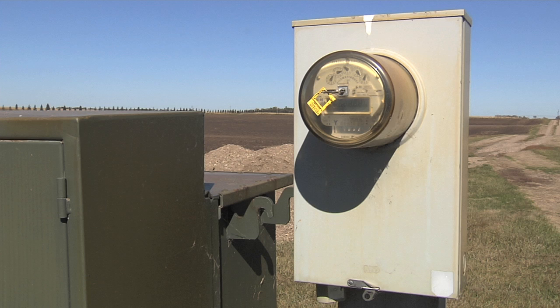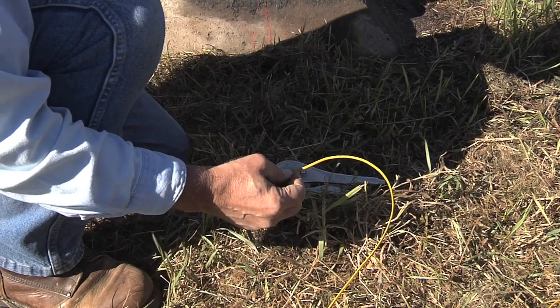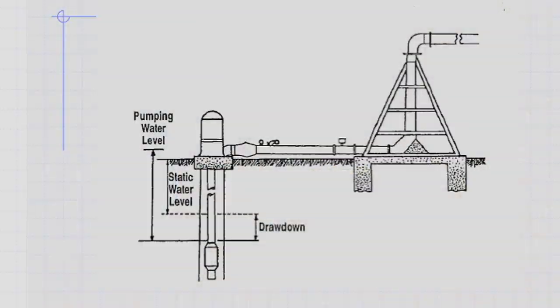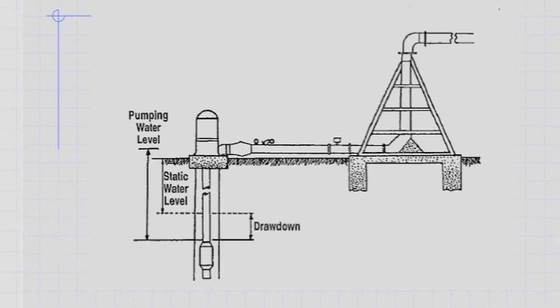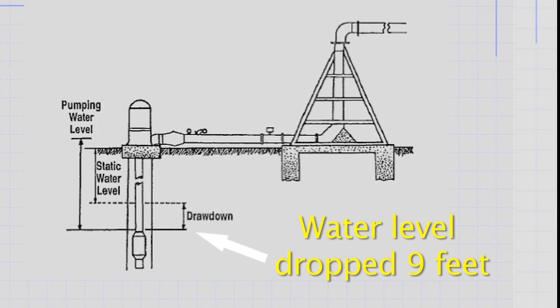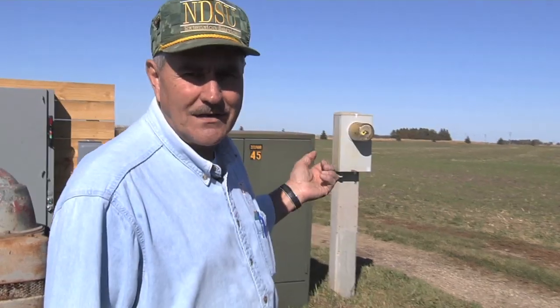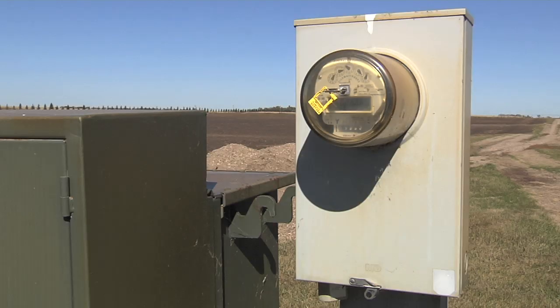And then when we get our electrical reading, we can compare the two and determine what the efficiency of this pumping plant is. It says 186, and we started at 162, so that means we've got 24 feet of pumping water level. So at 600 gallons a minute, this has only dropped 6 feet, which is a very good well. Or from 15, I should say, that's 9 feet, so you're getting quite a bit of water for a small amount of drawdown.